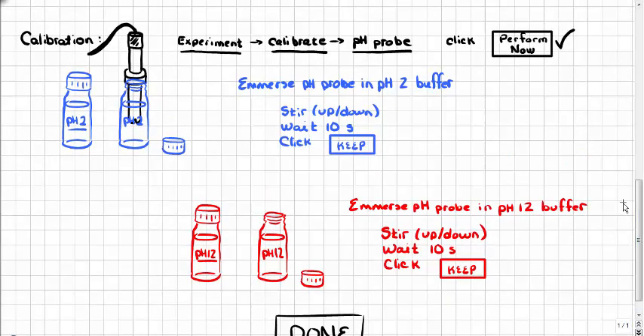Okay, so you'll take the top off that pH 2 buffer and insert the pH probe directly into the vial, and then it's important that you also stir, and the only way to really stir is to move in an up and down direction to keep fresh solution passing by the pH probe. All right. Typically, it's necessary to wait approximately 10 seconds before accepting this particular value. What we're doing here is showing the computer what a pH 2 actually looks like, and then it will use this as part of the calibration, but it'll need a second point that we'll get to in a second.